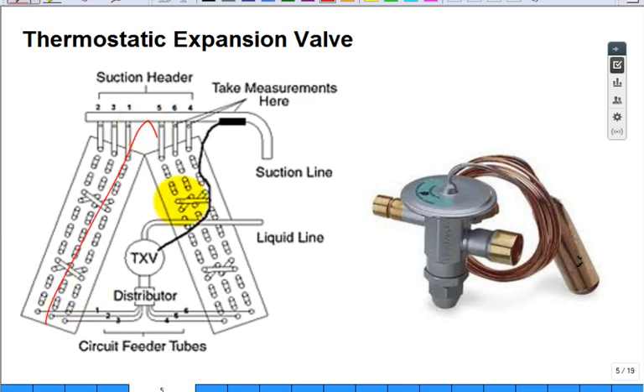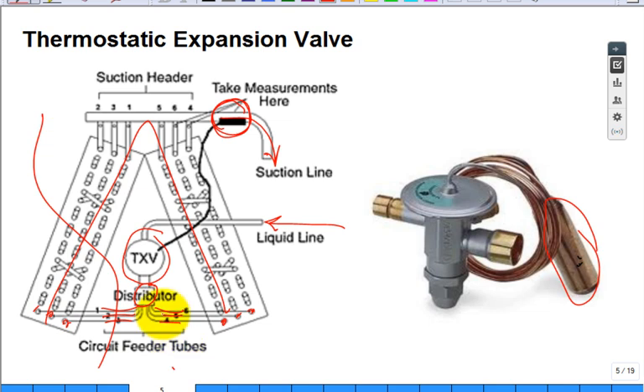So here is another picture of that, what they call A coil. The liquid line brings the fluid up. It goes real close, a thermostatic expansion valve. I passed around one for air conditioning application here. This has got a bulb on it. You move that bulb so it can sense the temperature of the refrigerant vapor leaving. If it's too hot, it opens up. If it's too cold, it closes. It's a control mechanism. And you have a distributor to, here it's showing you to throw it in six places, different locations, in the evaporator coil so you have a good distribution of heat transfer. The air comes up, passes like that, and it's cooled. Any moisture collects and condenses and drains down.